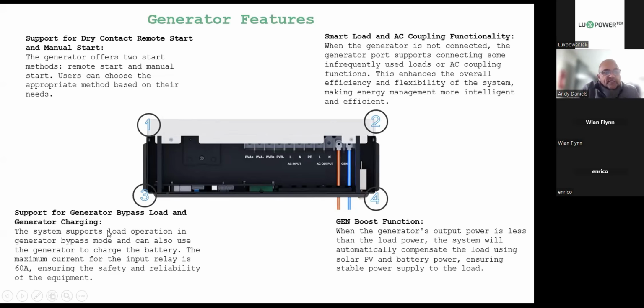The system supports load operation in generator bypass mode and can also use the generator to charge the battery. The maximum current for the input relay is 60 amps. Remember, we spoke about that earlier. The maximum power that you can put in here is 60 amps DC, load and charge the batteries. And then point number 4 is a very cool feature that we've just added to the 6 kilowatts. As a matter of fact, we've got it on our other machines as well.